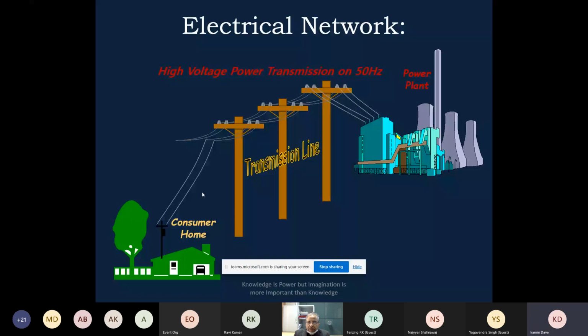This is normally the power generation, transmission, distribution. Power generation specifically is done at medium voltage like 6.6 kV, 11 kV. It depends on how much capacity the generator has, on the current carrying capacity of the conductor, the ampacity. It depends on the voltage level of the generator, the current capacity of the generator, and the size of the machines.